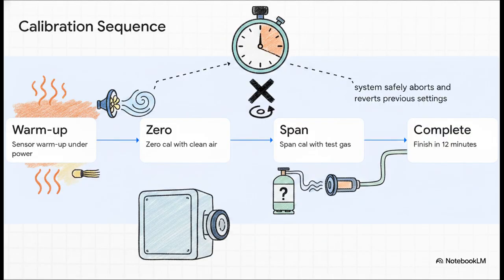You also have to keep up with the safety sensors inside the enclosure, like the combustible gas detectors. The calibration process is pretty standard. You warm them up, set the 0 with clean air, and set the span with a known test gas. But here's the catch. That entire sequence has to happen within a strict 12-minute window. If the clock runs out, the system safely aborts and just reverts to its old settings. That way, a life safety sensor is never left hanging in some dangerous, half-calibrated state.